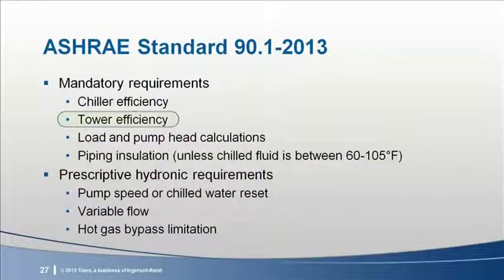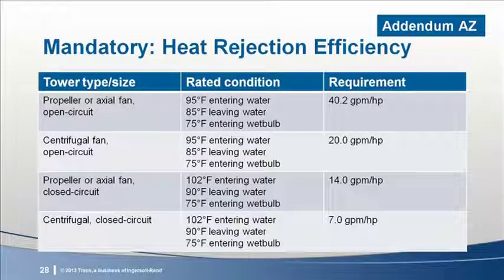In the mandatory requirements, we have the next hurdle, cooling tower efficiency requirements. Cooling tower efficiency is measured in GPM per horsepower at rated conditions. For the rest of today's presentation, we'll be focusing on systems using open circuit propeller fan cooling towers, the predominant type of cooling tower chosen for water-cooled HVAC systems. In 90.1 2013, propeller or axial fan open circuit cooling towers had the only change. They went from 38.2 GPM per horsepower to 40.2 GPM per horsepower. That's about a 5% increase in stringency.